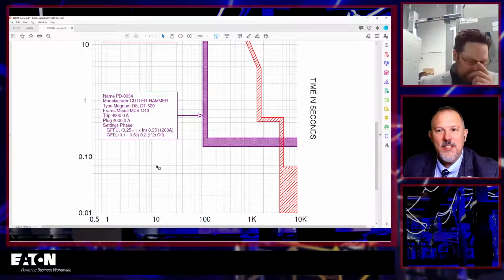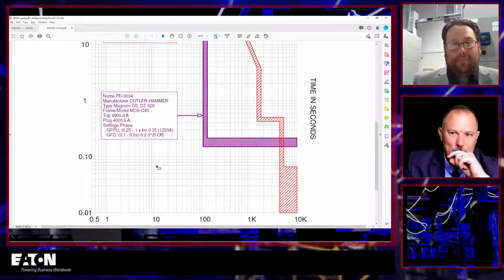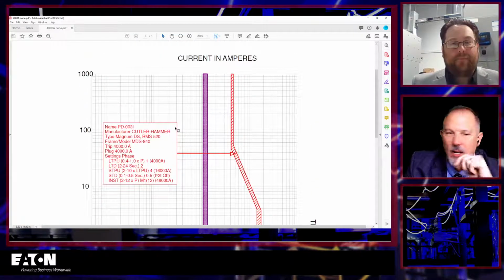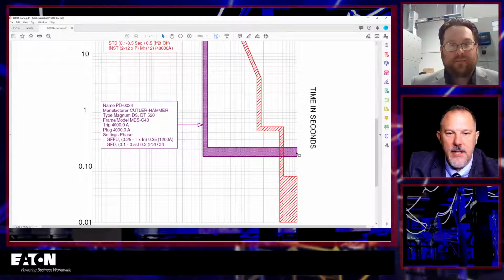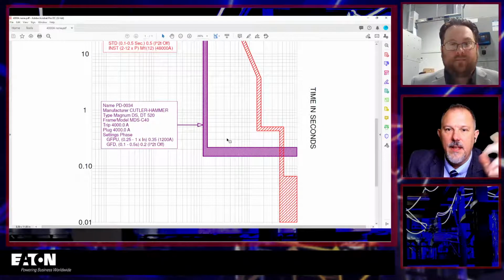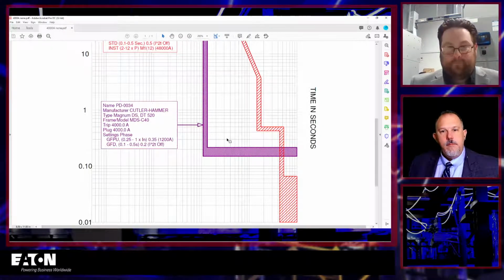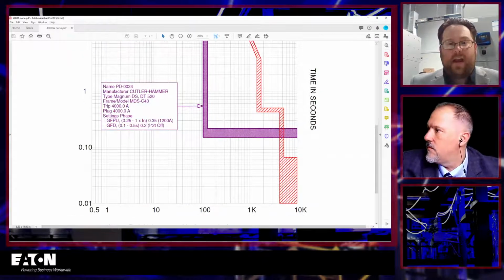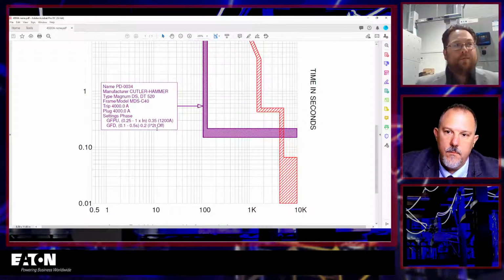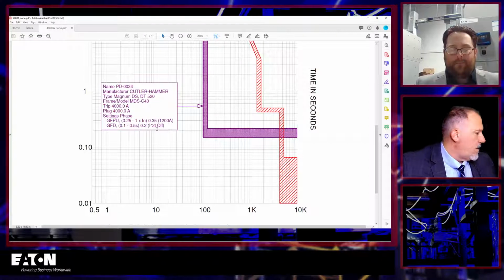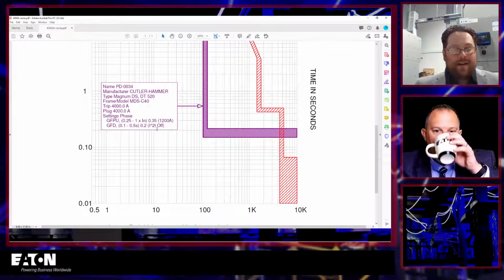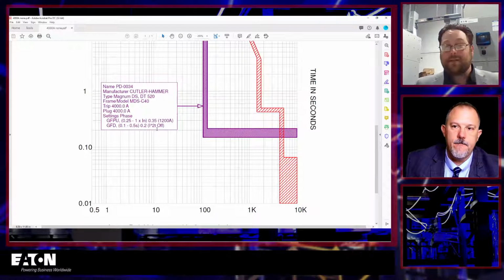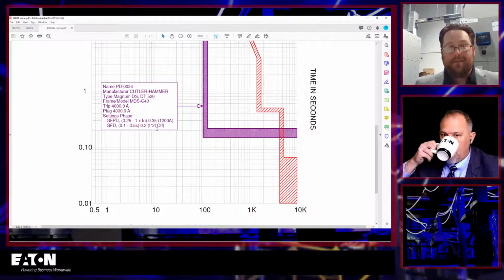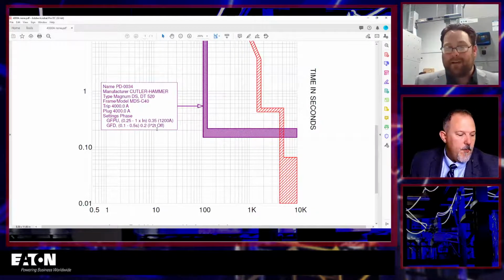So I call these curves the hockey stick, and that's basically what it looks like. There's your 4,000 amp pickup, and then this is down at 1,200 amps, and it's basically a hockey stick looking at anything that doesn't add up to 0. Absolutely, and that is so useful. When you have a coordination study done, obviously you want all your devices to coordinate from a phase perspective, but also from a ground fault perspective.